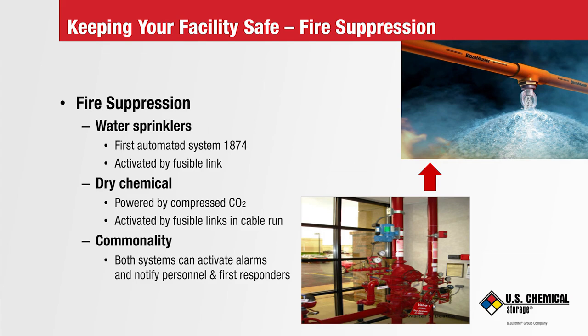In a wet type, the pipes are full of pressured water. In northern and southern hemisphere freeze zones, care must be taken so the incoming water supply is buried deep below the local ground's frost line and insulated or wrapped in electric heat tape to prevent water from freezing. The wet sprinkler system requires the interior of the building to be heated in the winter.